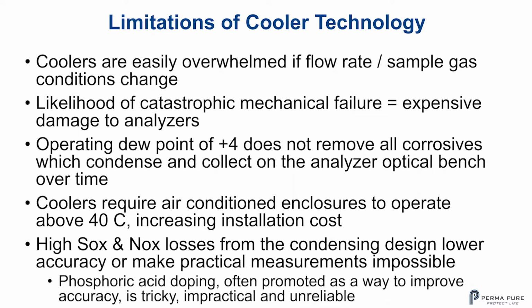So it still allows enough moisture and enough of the gases that make it possible for acids to collect ahead of the cooler. And the coolers require air-conditioned enclosures to operate above 40 degrees C, increasing installation costs. You also have high SOx and NOx losses from the condensing design that lowers accuracy or makes practical measurements impossible.